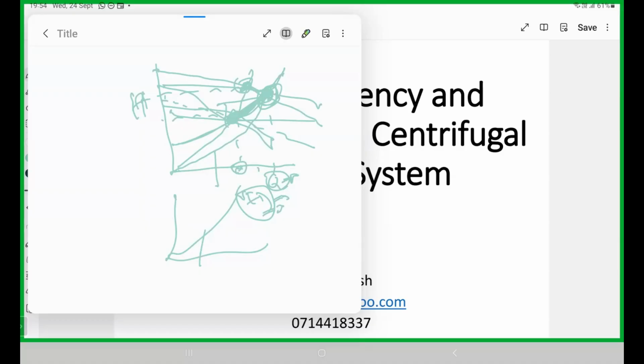The fire pump is the same, but the important difference is the gland and the sealing method. For water pumps we have a seal, either a mechanical seal or a gland. For the fire pump, it should be gland type. The fire pump is low head operation, and the motor capacity should be high. For water pumps we generally say 10 percent, 1.1 times more than this, for motor loading. The fire pump and sealing method is the standard to select, I think.